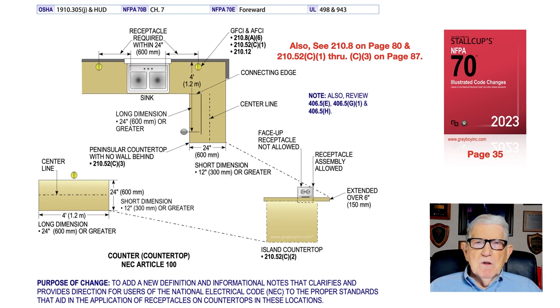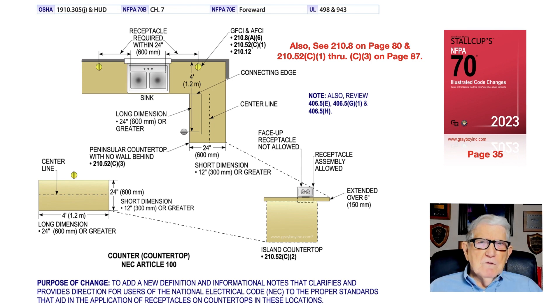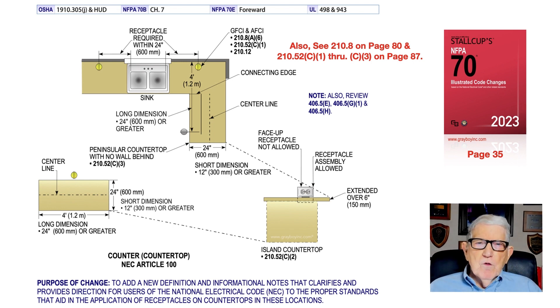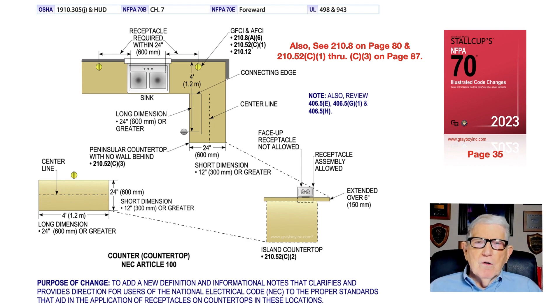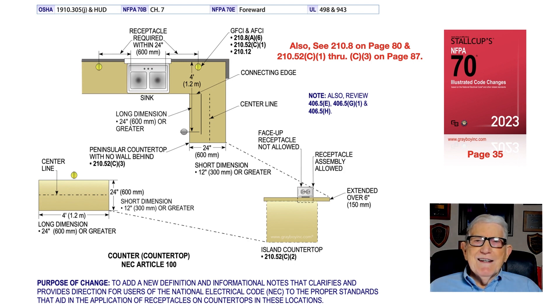One important point is that to be sharp on countertops, peninsulas, and islands, you should review UL-498 and UL-943, as well as Article 406, specifically 406.5E, 406.5 G1, and 406.5H. Reviewing these will clarify exactly what is required when receptacles are installed on countertops. For GFCI and AFCI protection details, see 210.8 A6, 210.52 C1, and 210.12.